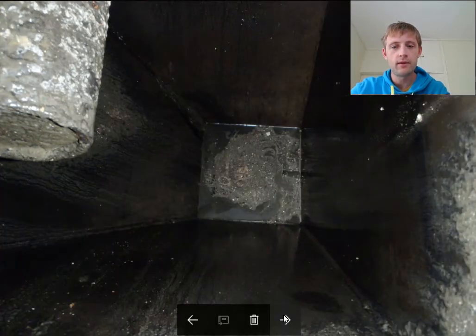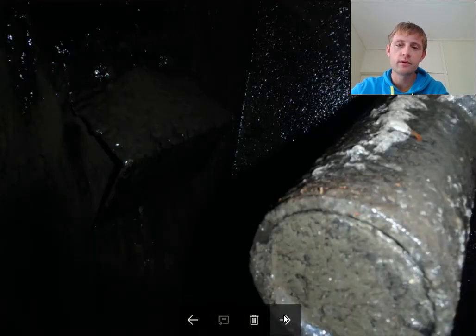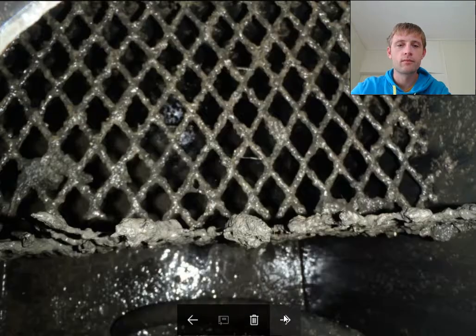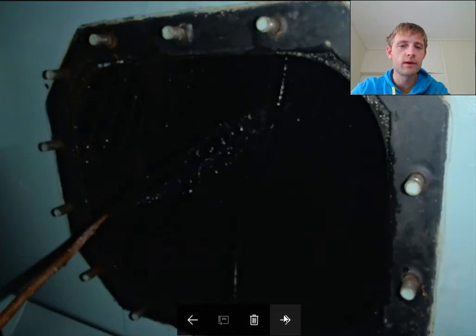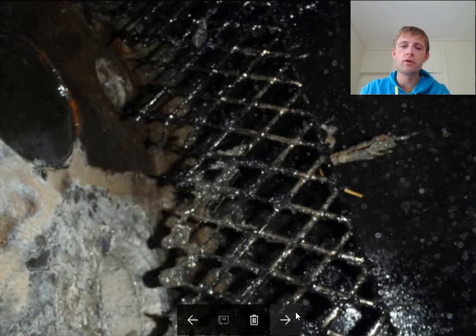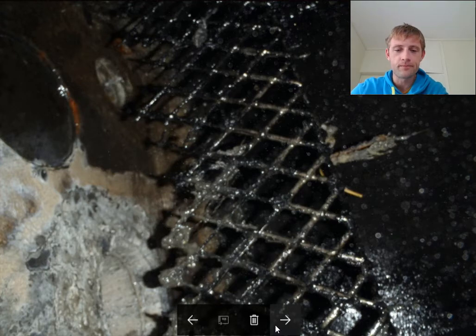These sewage tanks have a special coating — never weld around these tanks. Sometimes, if the sewage treatment plant is not working properly, you need to open it and check what is going on inside. There are also special test kits from which you can test chlorine levels, sediment, and how your sewage plant is working overall.